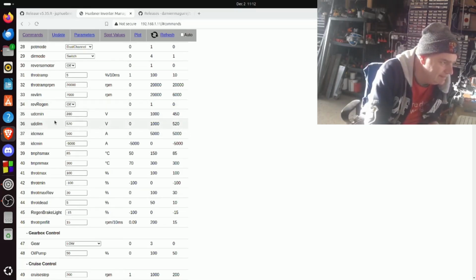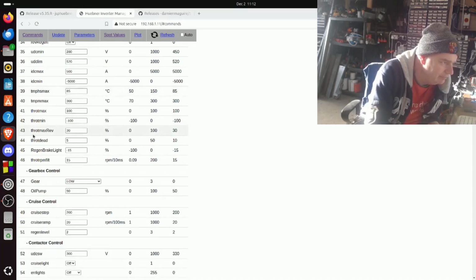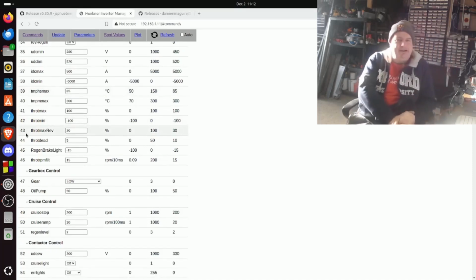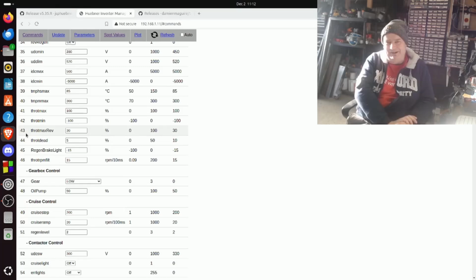Let's run down to our other settings. We have Trot Max reverse, parameter 43. It means what it says on the tin: the maximum throttle setting you'd like in reverse. Some people don't want full speed in reverse, so you can set what percentage of torque or throttle command is available in reverse gear.